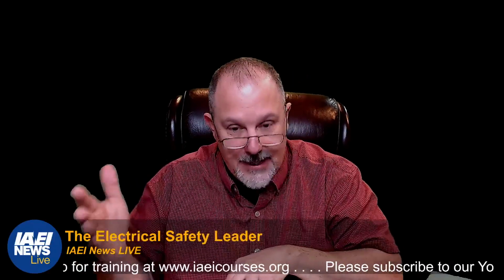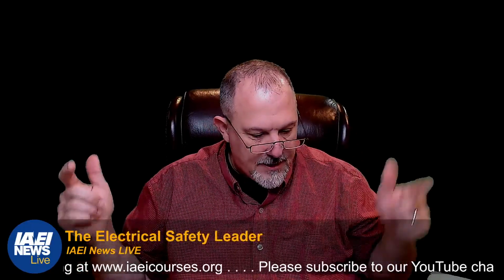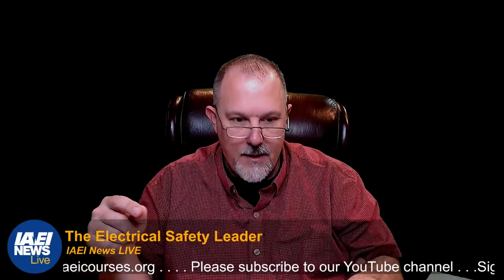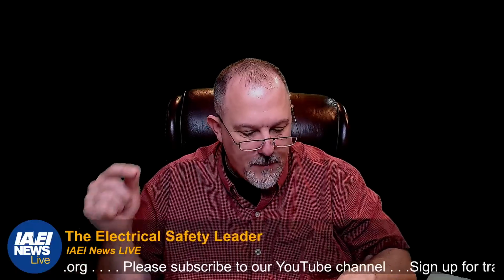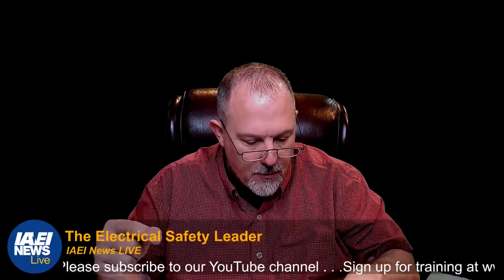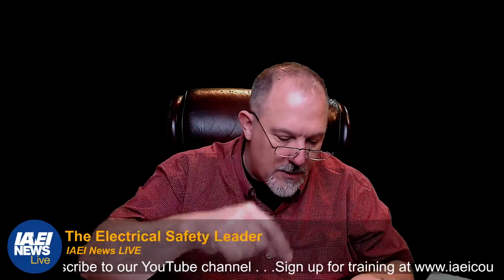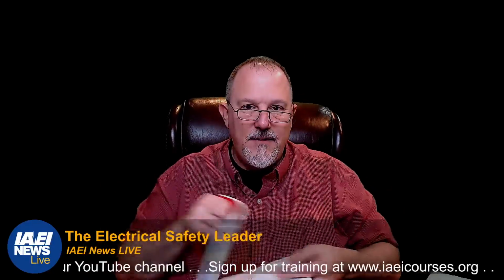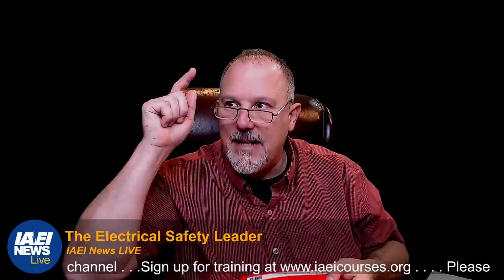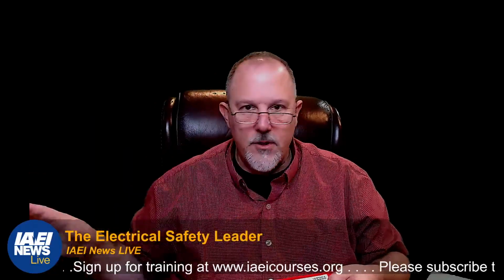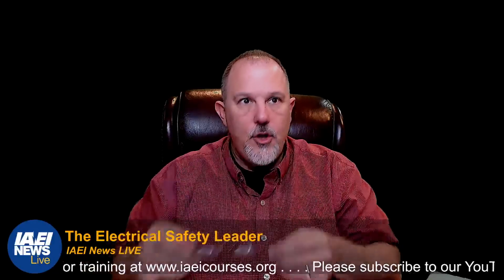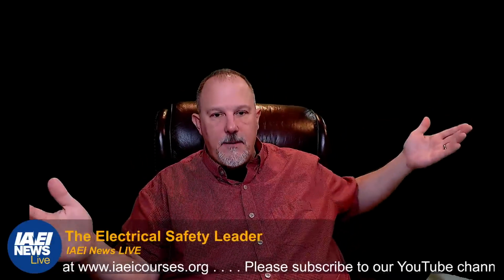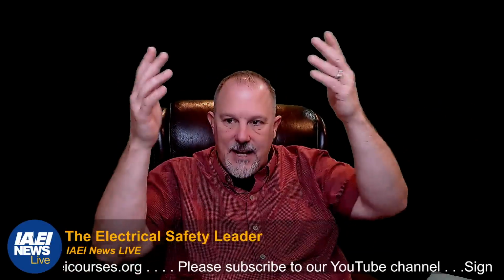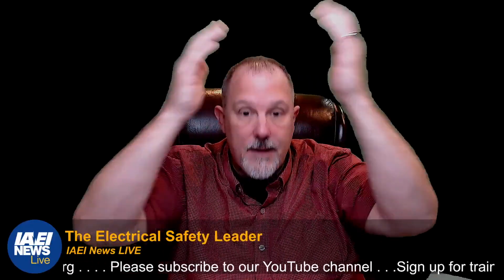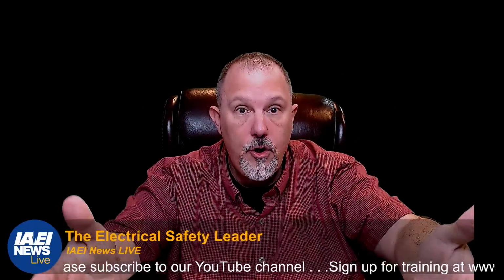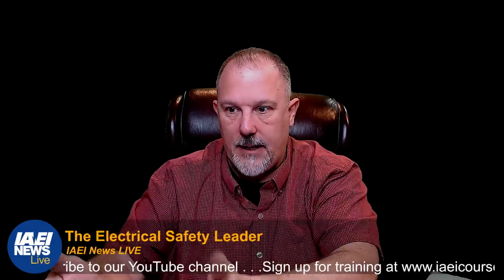70E requires in section 110.5 that the employer shall implement and document an overall electrical safety program that directs activity appropriate to the risk associated with electrical hazards. So with 70B, if you have panel boards in your facility, you don't just say, I'm going to get a copy of 70B and that's my maintenance plan. No, you need to create a maintenance plan.